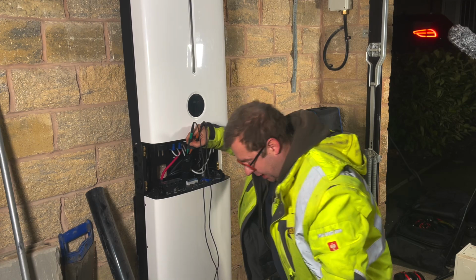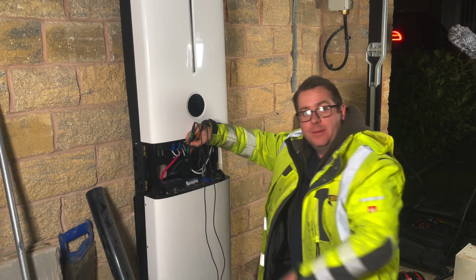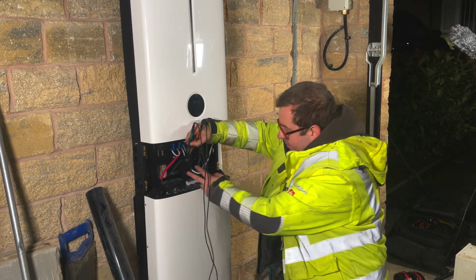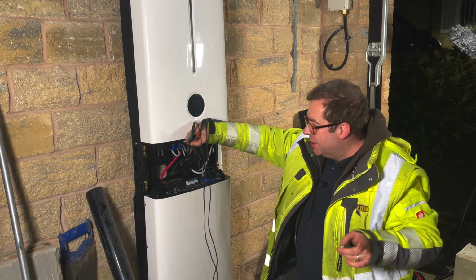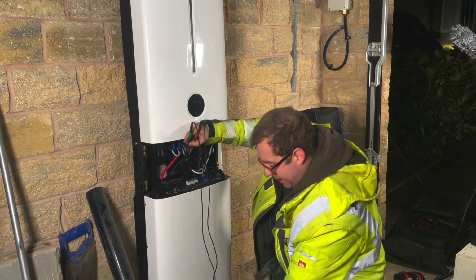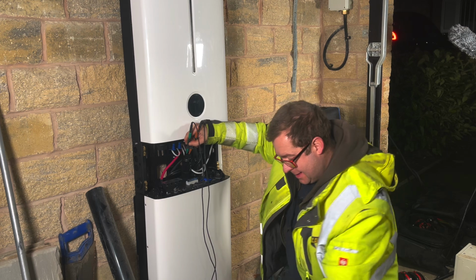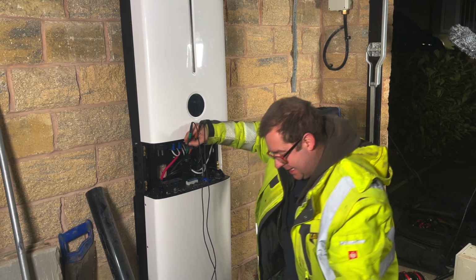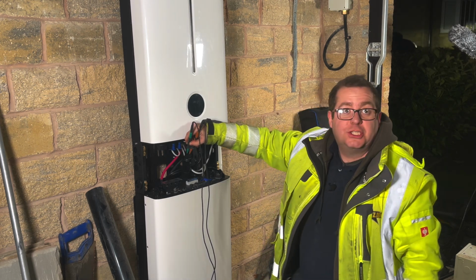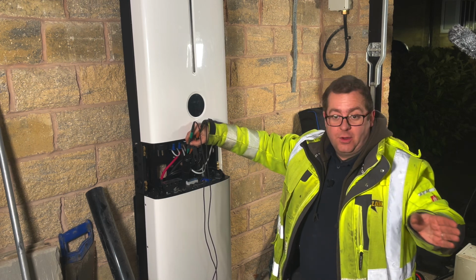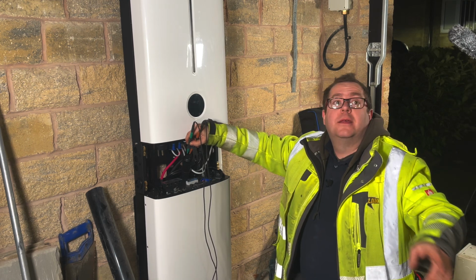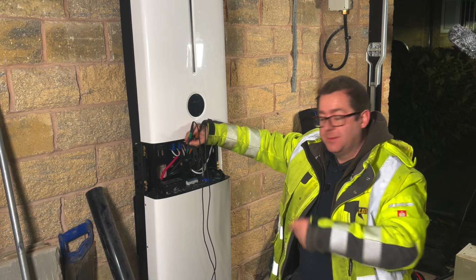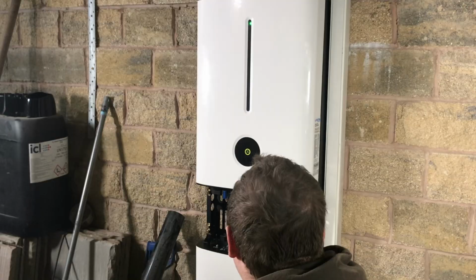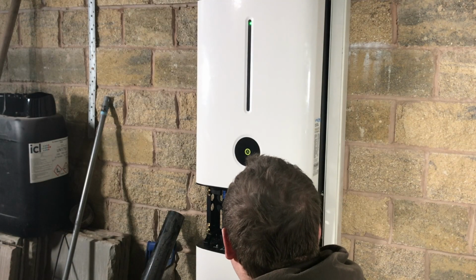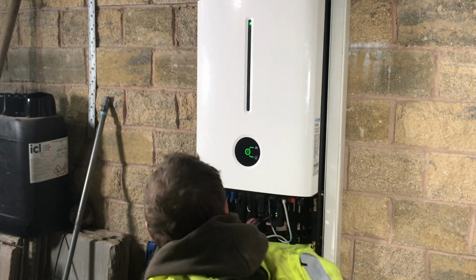So I'm just checking the polarity of the incoming plug. I've disconnected the incoming plug from the inverter, turned on the supply, I'm checking the polarity, and then I'm going to do a Zs test just to check that you've got adequate earth in. So in the event of a fault, somebody cuts through the cable or there's an electrical fault, it will trip the devices downstream in line with the regulations.